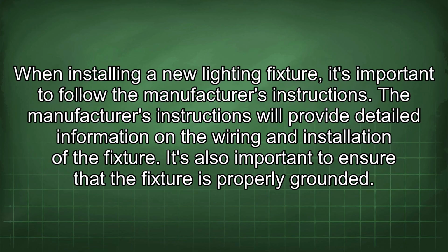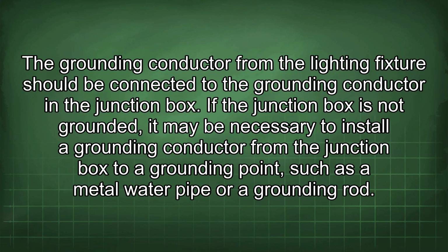When installing a new lighting fixture, it's important to follow the manufacturer's instructions. The manufacturer's instructions will provide detailed information on the wiring and installation of the fixture. It's also important to ensure that the fixture is properly grounded. The grounding conductor from the lighting fixture should be connected to the grounding conductor in the junction box. If the junction box is not grounded, it may be necessary to install a grounding conductor from the junction box to a grounding point, such as a metal water pipe or a grounding rod.